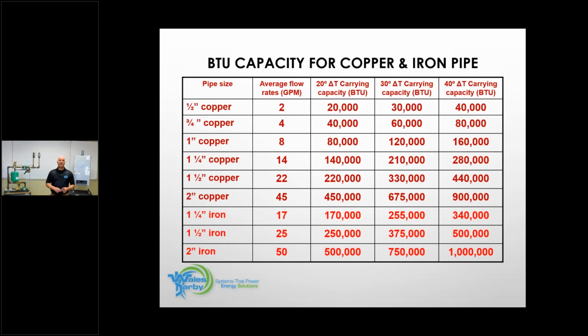This right here is very important to have. I would screenshot this if you don't have it already. This goes through pipe sizes from 1/2 inch copper, 3/4, 1 inch down the line, all the way up to 2 inch copper, and then we get into iron pipe, so you have an understanding at a typical delta T what a pipe will carry.